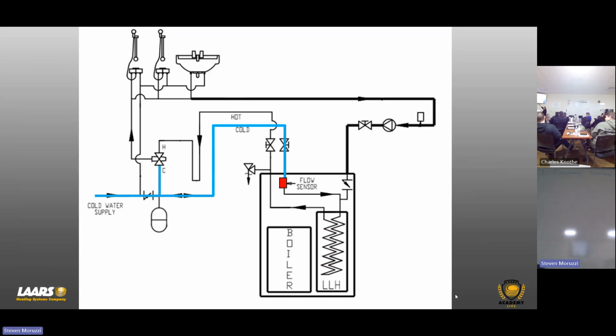Check valve required. So we give you this mixing valve, right? Cold water here, going to come past the flow sensor, and we're going to provide heat out to the hot port or hot tapping on the mixing valve. So I'm showing 140. But I gave you guys the example that we could see 180, right? If it's a 0 degree night, a 10 degree night, and during the evening, I've got a 3-zone home. They've been running that heat exchanger, that potable indirect shell and tube design could be 180 degrees. Now it's first thing in the morning and someone gets up to go jump in the shower. And I could, instead of sending 140, I could be sending 180 out. So we definitely need that mixing valve, that anti-scald tempering valve out there, okay? And now, obviously, you blend that down for your showers, your faucets, your sinks, etc.